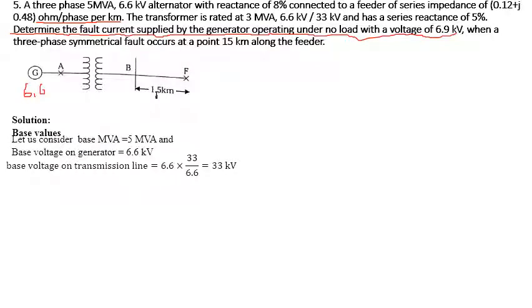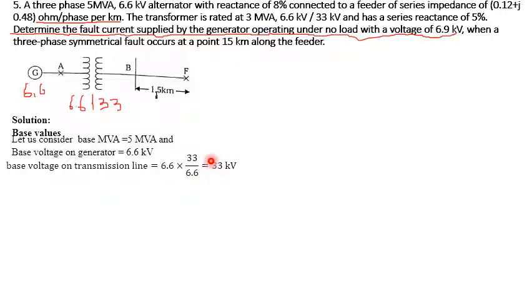Then we have to calculate the voltage on the transmission line side. The transformer rating is 6.6 kV / 33 kV, so the base voltage on the high-voltage side equals the low-voltage base of 6.6 kV multiplied by the transformer turns ratio: 6.6 × (33 / 6.6) = 33 kV. So the new base value on the transmission line side is also 33 kV.